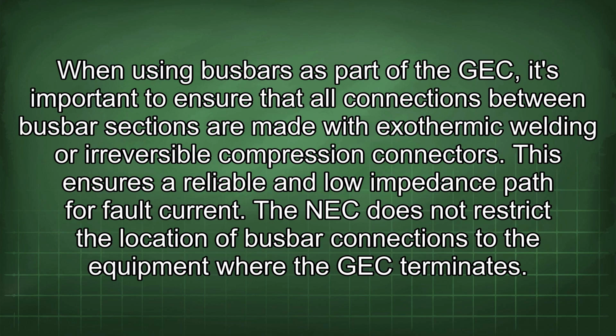When using busbars as part of the GEC, it's important to ensure that all connections between busbar sections are made with exothermic welding or irreversible compression connectors. This ensures a reliable and low impedance path for fault current. The NEC does not restrict the location of busbar connections to the equipment where the GEC terminates.